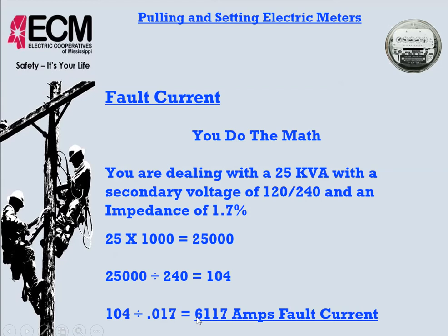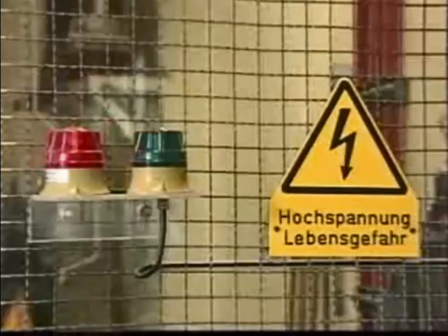on our system. So in a household, on a residential meter base, you could have up to 6,117 amps of fault current with a 25 kVA and 1.7% impedance. So we have a video here that we're going to watch, and it shows us what could happen if we're exposed to that type of fault current, in real time.